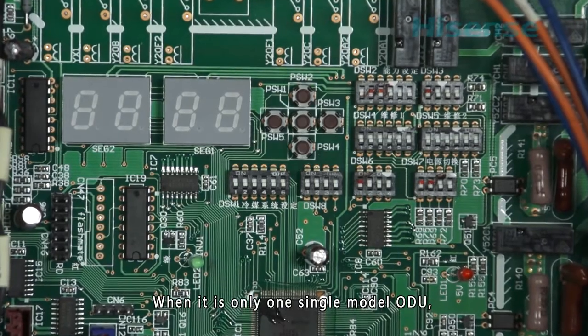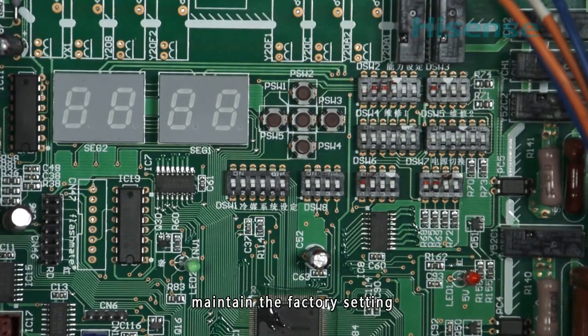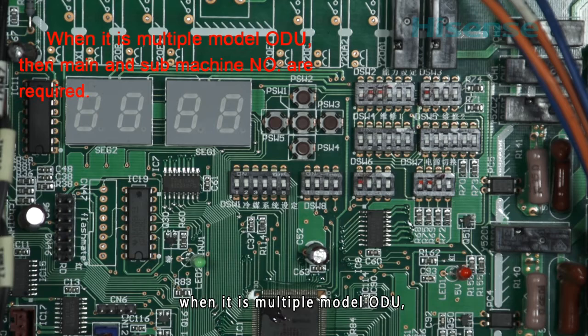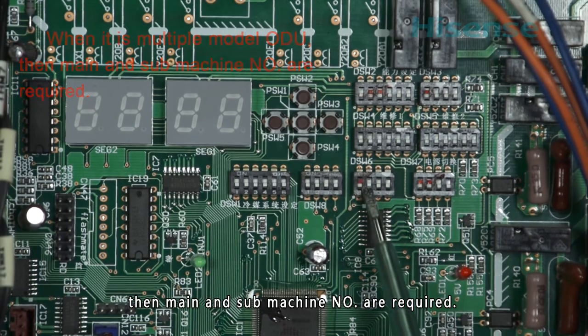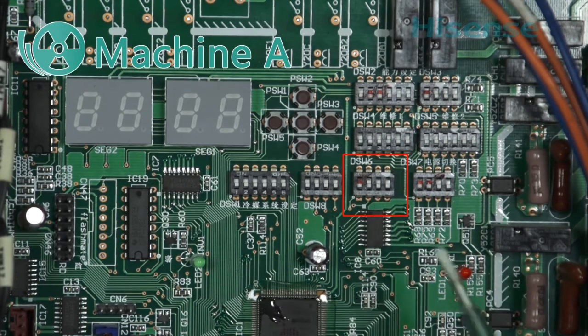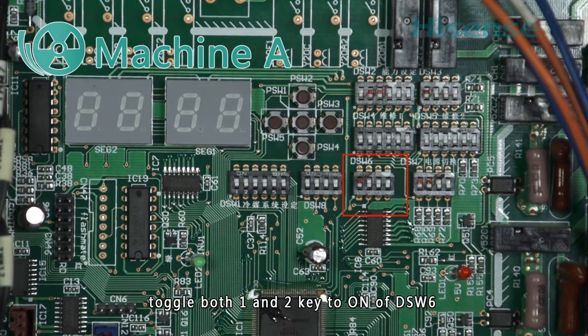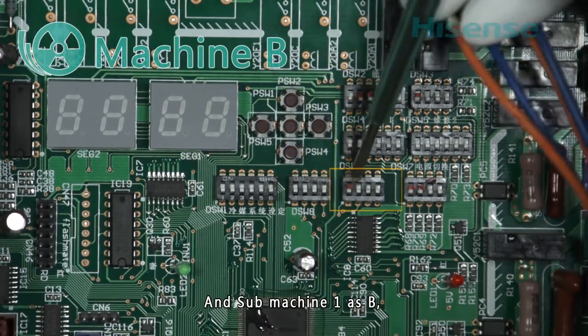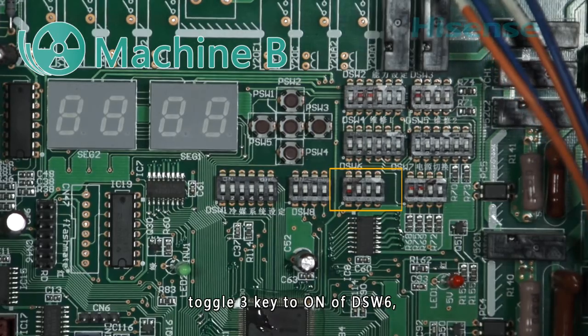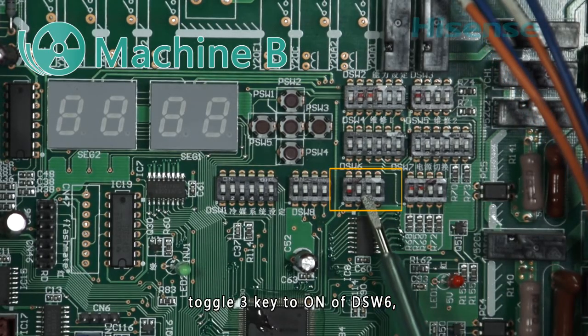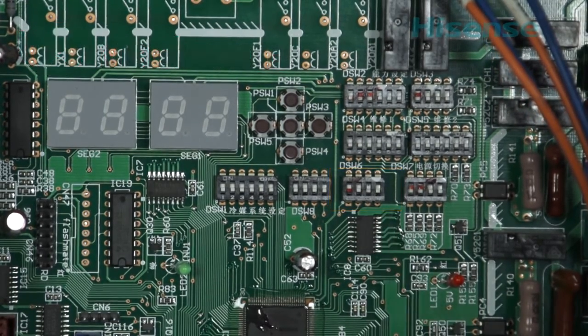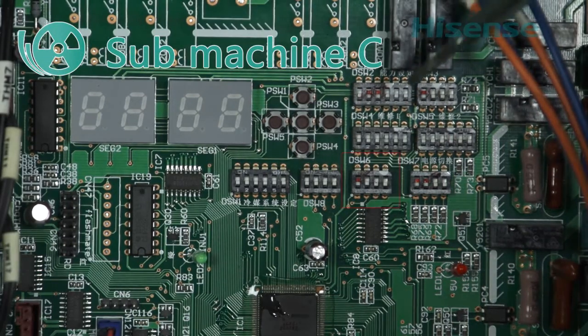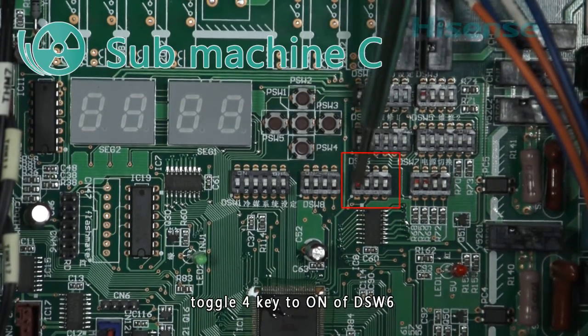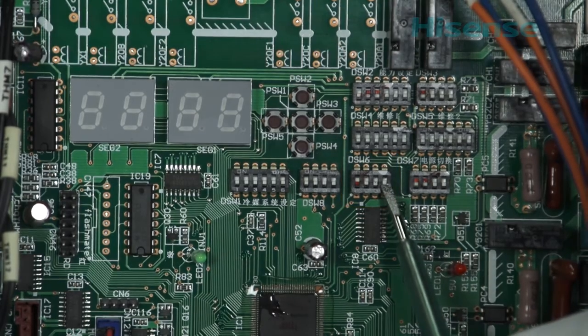When it is only one single model outdoor unit, maintain the factory setting. When it is not only one single model outdoor unit, then main and submachine number are required. Set the main machine as A. Toggle both 1 and 2 key to on of DSW6. And submachine 1 as B. Toggle 3 key to on of DSW6. Submachine 2 as C. Toggle 4 key to on of DSW6.